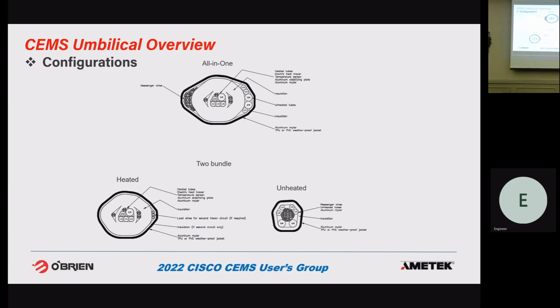So there's more upfront cost with the 2-bundle approach, but over the life of a stack of 40 or 50 years, where you may be replacing that heat trace 2 or 3 times depending on maintenance, it's definitely a less expensive option. Any questions on the 1 or 2 bundle approach?